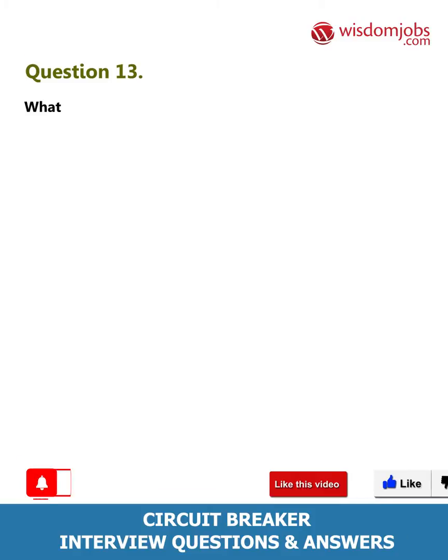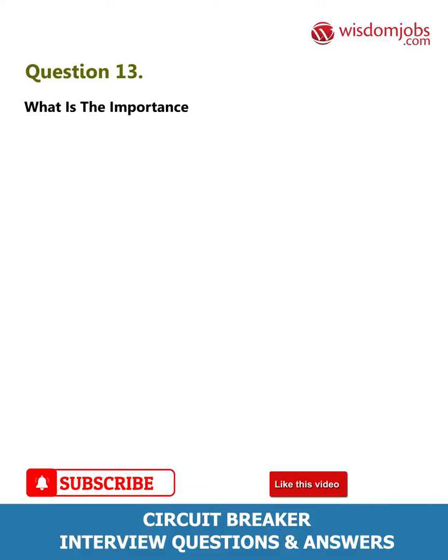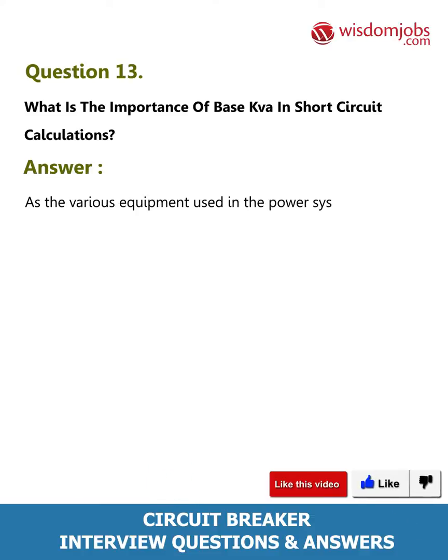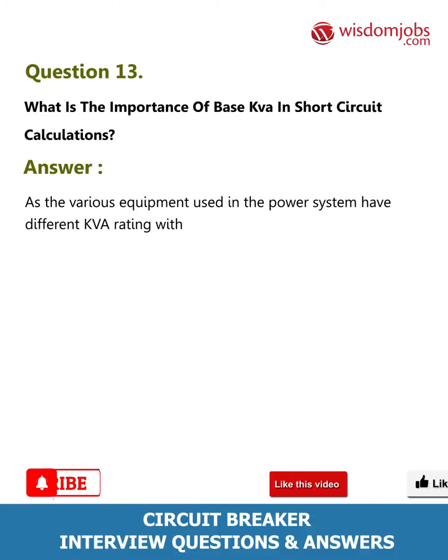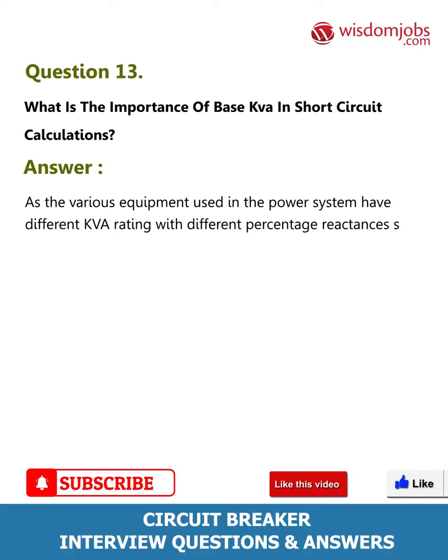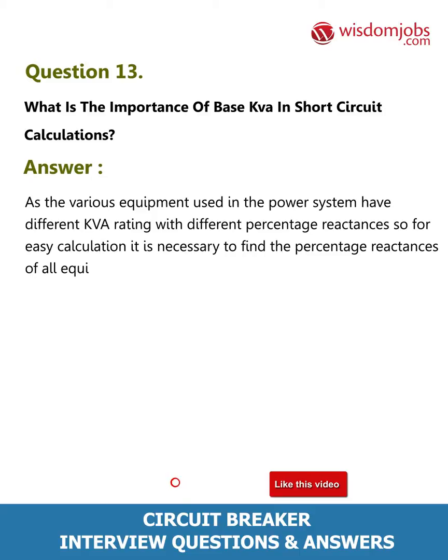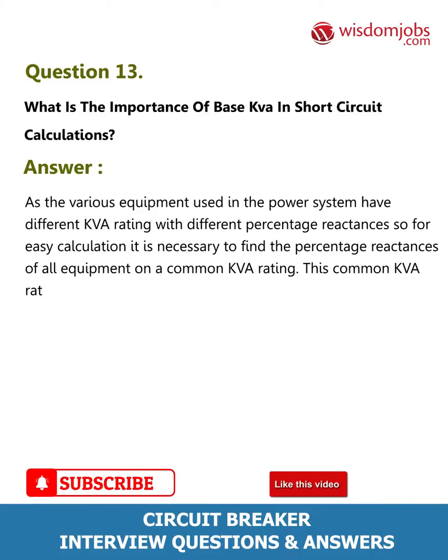Question 13: What is the importance of base KVA in short circuit calculations? Answer: As the various equipment used in the power system have different KVA ratings with different percentage reactances, for easy calculation it is necessary to find the percentage reactances of all equipment on a common KVA rating. This common KVA rating is known as base KVA.